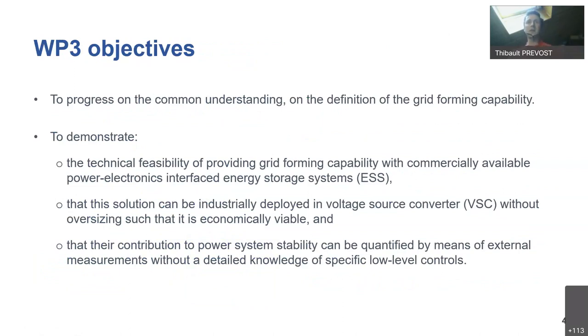So the objective was to progress on the common understanding and also on the definition of this grid forming capability. It's also very much in line with what Deepak mentioned in his previous presentation. In Migrate, we were very much control oriented. Now we try to see how we can define grid forming based on grid requirements, or performances. So the objective was to show that we can provide grid forming capability with commercially available energy storage systems, that it can be deployed without oversizing, and that the control performances can be assessed without knowing the control, just with external measurements.